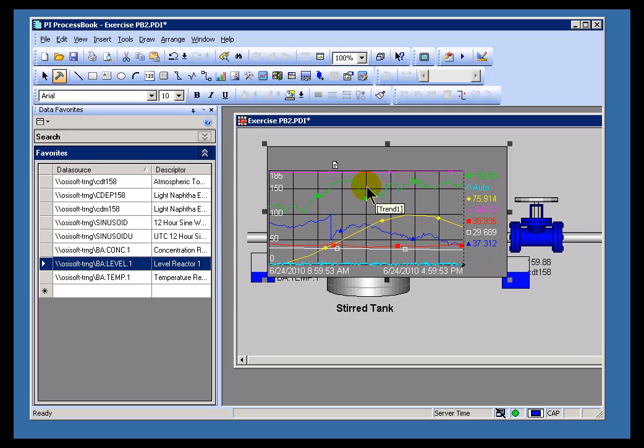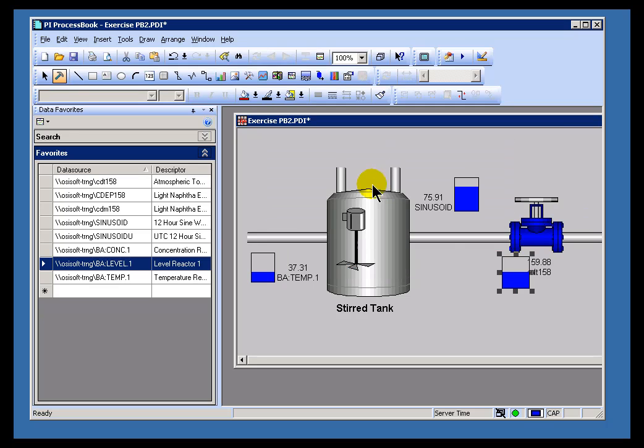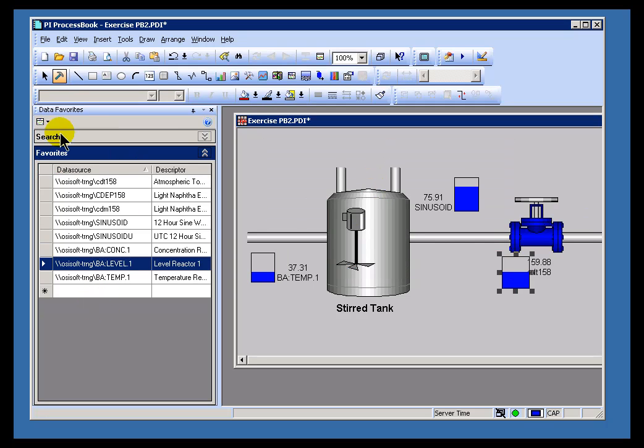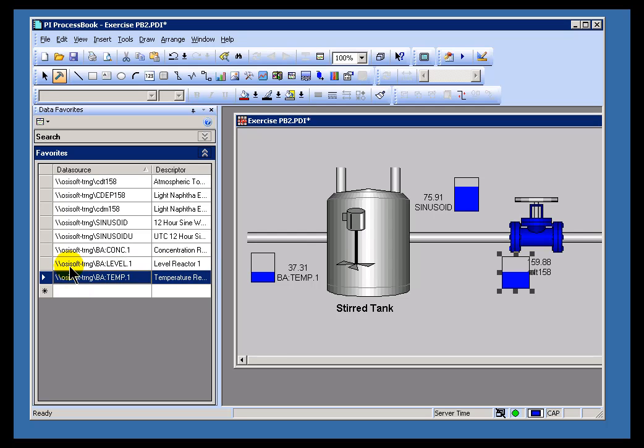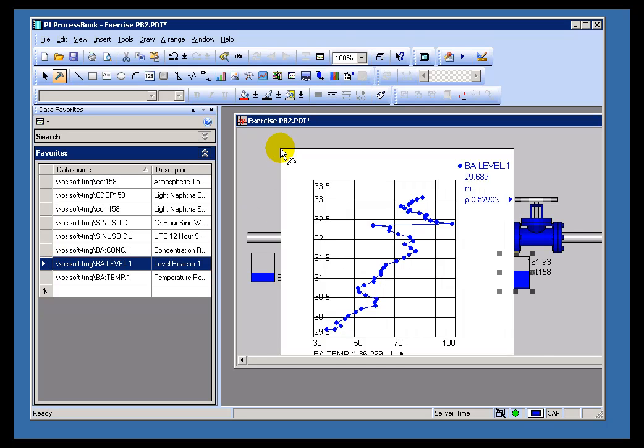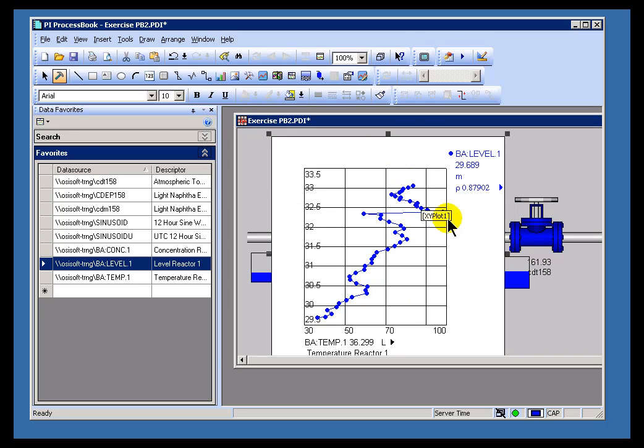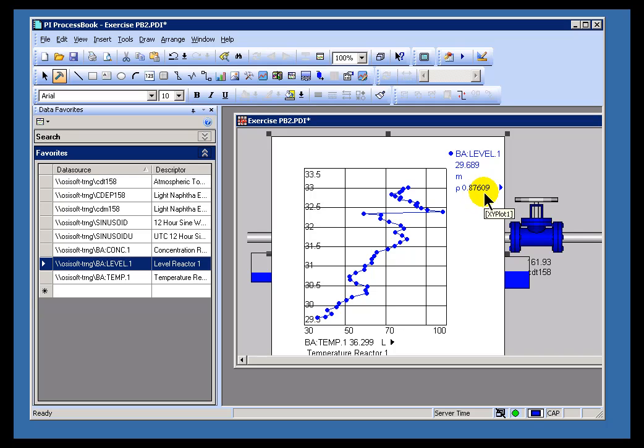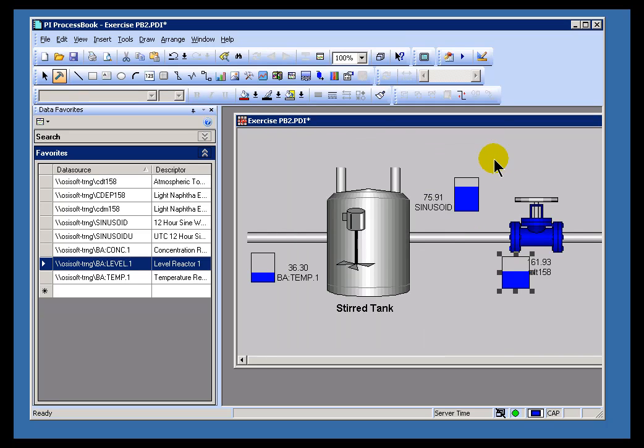I'll show you something I find particularly compelling is with the XY plot, if you choose XY plot as the default, what you've got now here is a very nice little correlation engine. I can say, well, let's see if there's a relation between level and temperature or level and anything on here. And, if I click, bring that over we immediately now have an XY plot that shows me, well, in this case, there is a fairly strong correlation, a coefficient of correlation of 0.87, which is an extremely high correlation.